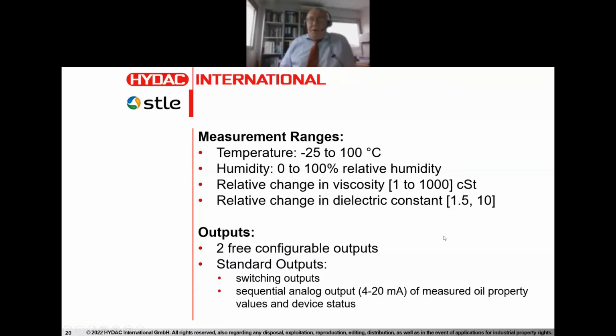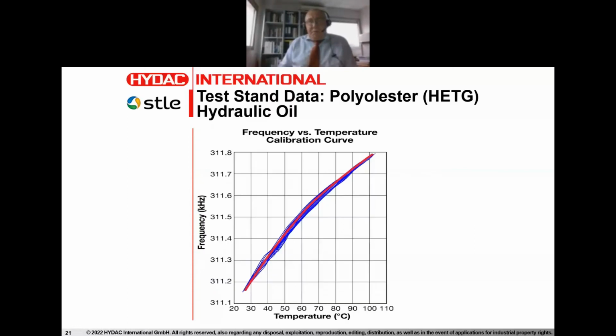The reason was that one of the basic specs for fluid acceptance for continued use is plus or minus 10% change in fluid viscosity. A 10% decrease means the fluid has been sheared and no longer possesses the appropriate load carrying capacity. On the other hand, an increase of 10% means that the fluid has polymerized enough that it's going to provide too much resistance to the system's operating components. The relative change in dielectric constant is from the absolute value of 1.5 to 10, with two freely configurable switching outputs, so we could actually act upon the signals that we received.